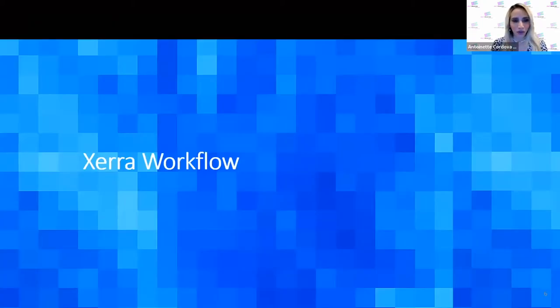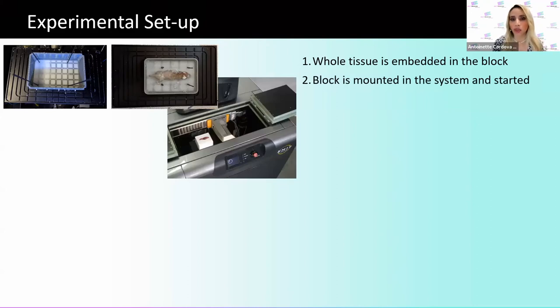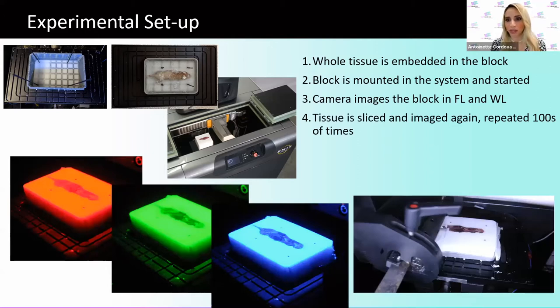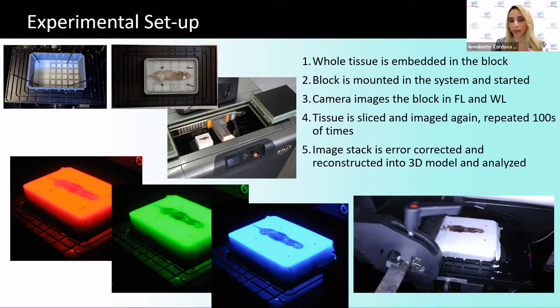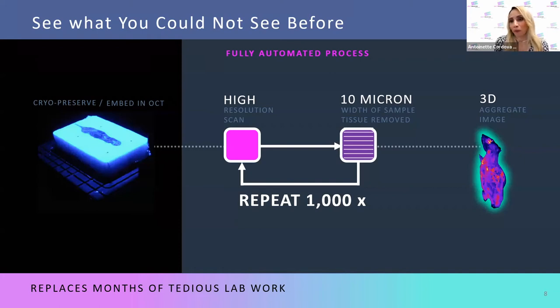The experimental workflow: a whole tissue is embedded with OCT, then frozen, and the block is mounted into the system. We offer five different fields of view with different resolutions depending on which you choose. A camera images the block in fluorescence and white light, and this is repeated hundreds of times. At the end of a run, you get an image stack reconstructed into a 3D model — a high-resolution scan with 10 micron width of tissue removed each slice, yielding a 3D reconstructed image relatively quickly.